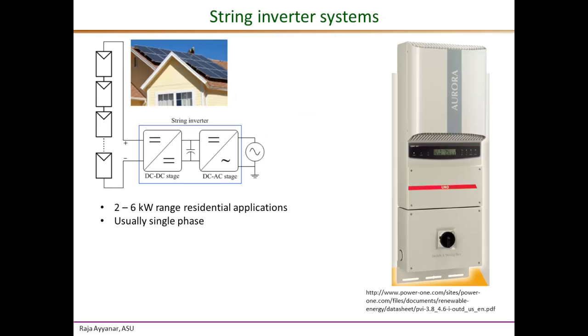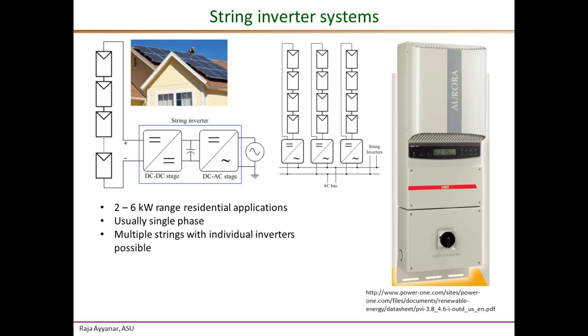String inverters are used in residential rooftop applications, typically single phase in the range of 2 to 6 kilowatts. The name comes from the fact that these inverters interface a string of series-connected PV modules to the grid. Multiple strings on a rooftop can each be connected to an individual string inverter, providing maximum power tracking for each string separately. String inverters provide string-level MPPT, which is better than central inverters, but still not optimal compared to microinverters.